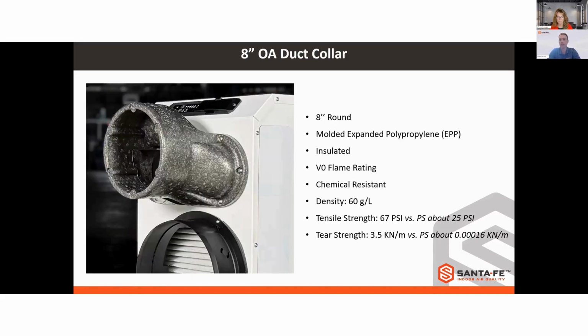It's called expanded polypropylene. And it's kind of like a foam. It's lighter than a hard plastic, but it's insulative, so you don't need to worry about insulating the strange shape as it goes from the round to the oval of the machine. It has a V0 flame rating to meet all the requirements around anything in the airstream with a refrigerant in it. It's chemical resistant. The density is quite low, but really what shines on here is the strength of the duct. And so a couple ways to measure this is tensile strength. That's the kind of idea of pulling the duct apart. And it's about 67 PSI. And if you try to put that in perspective, PS is about 25 PSI. That's polystyrene, so that's styrofoam like you'd see in packaging and stuff like that. So it's almost twice as strong of just pulling it.